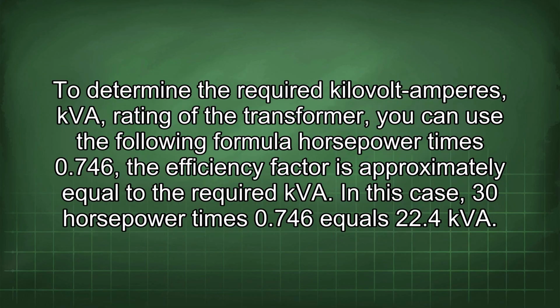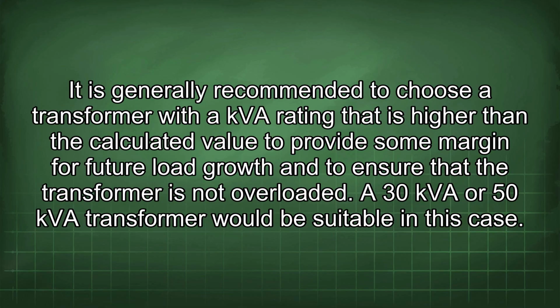To determine the required kilovolt amperes, or kVA, rating of the transformer, you can use the following formula: horsepower times 0.746, divided by the efficiency factor, is approximately equal to the required kVA. In this case, 30 horsepower times 0.746 equals 22.4 kVA. It is generally recommended to choose a transformer with a kVA rating that is higher than the calculated value to provide some margin for future load growth and to ensure that the transformer is not overloaded. A 30 kVA or 50 kVA transformer would be suitable in this case.